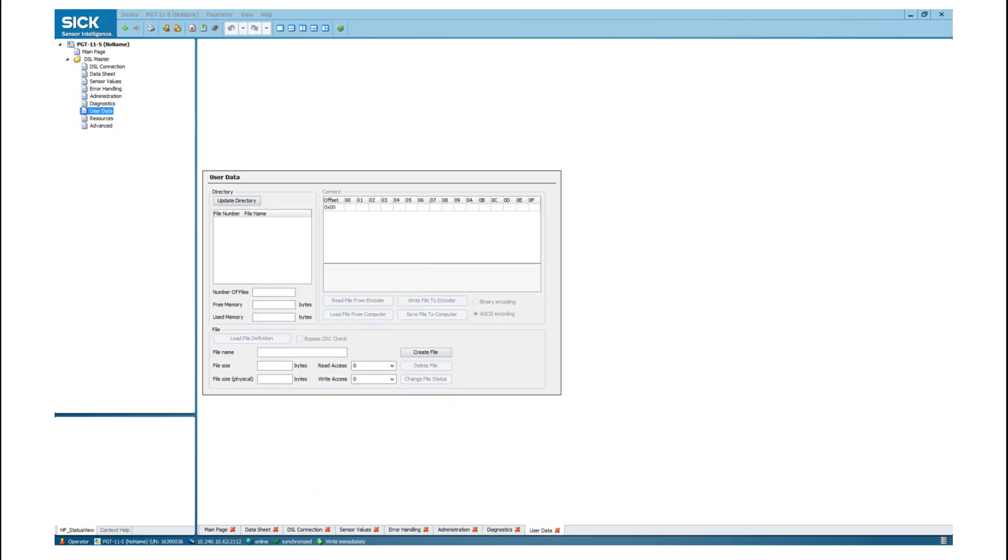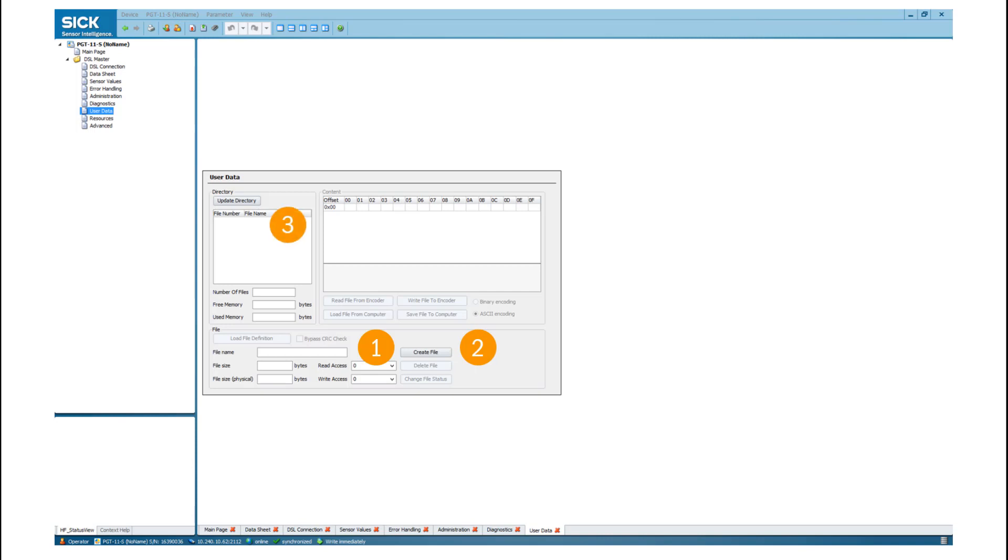To support functions like traceability or automated identification, you can store user-specific data in the sensor. The memory is handled like a file directory. First, please enter a filename. Second, press create file. Third, click on the file number and load file definition. Now you can enter the information you want to store inside the sensor.